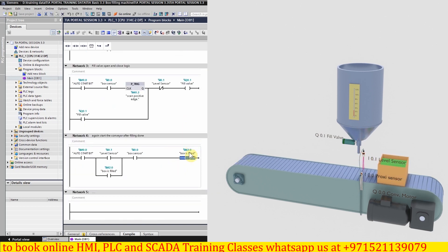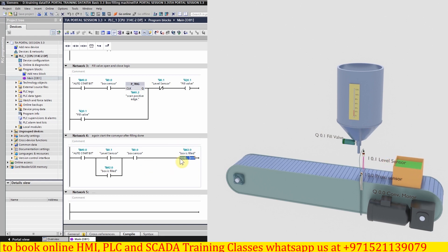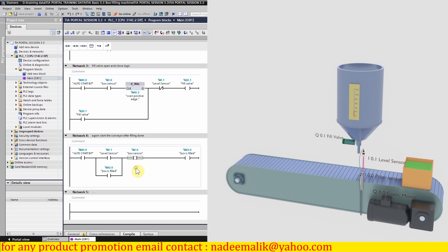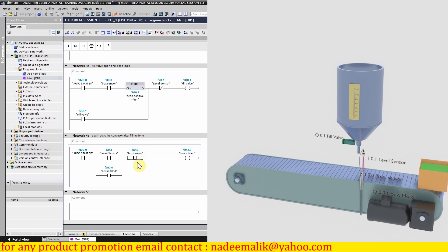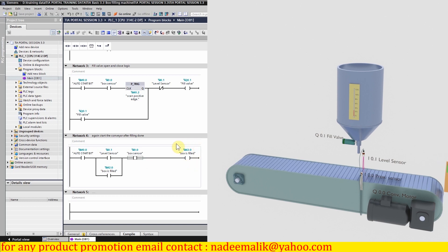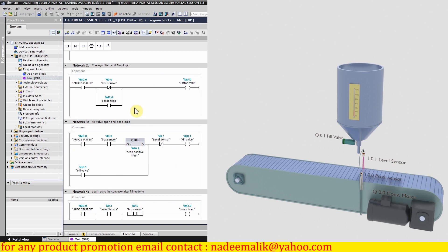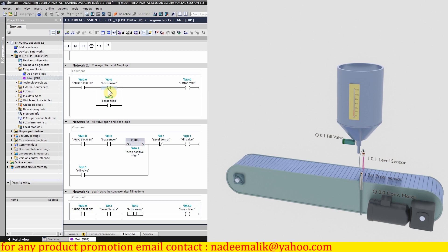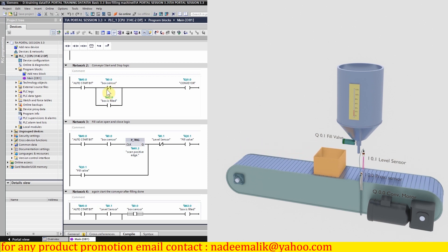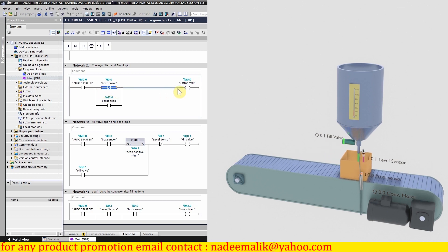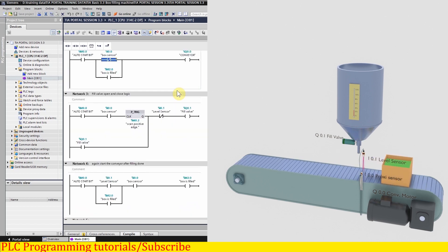As you can see, bit M 2.0 is latched on. Once the box clears sensor I 0.0, this bit opens up and unlatches the M 2.0 box-filled bit. As the box has moved away from sensor I 0.0, the normally closed contact closes again and keeps running the conveyor motor Q 0.0. This is the complete logic for today's project.